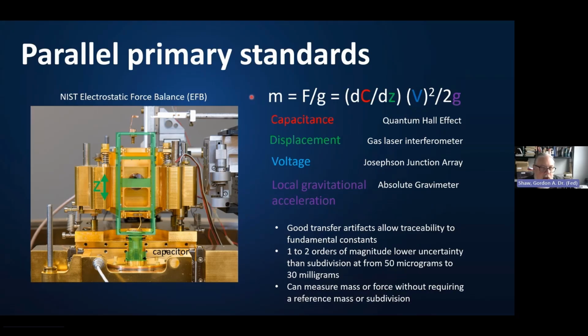We can use this measurement equation to determine the mass using measurements of capacitance, position, voltage, and local gravitational acceleration. Capacitance is traceable through the quantum Hall effect to fundamental constants. Displacement is measured using a stabilized helium neon laser interferometer, so this can be traced to the hyperfine splitting frequency of cesium-133 and the speed of light. Voltage is traceable to a Josephson junction array, and local gravitational acceleration is traceable to an absolute gravimeter. Because all of our quantities are traceable through the SI to these fundamental constants, we have a direct link to the fundamental constants in this instrument to create a primary realization.